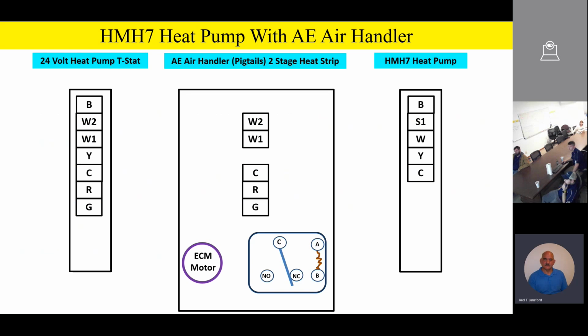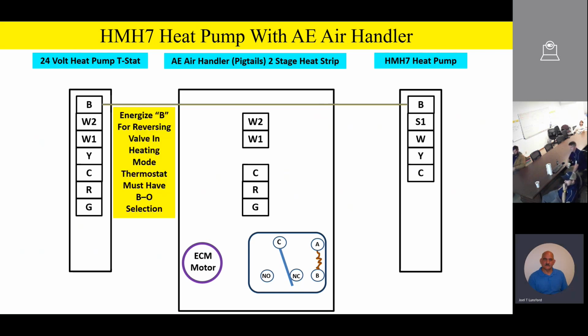Okay, so at this time, team, we're going to go ahead and just walk through wire for wire, hooking up the HMH7 with an AE air handler. And again, please remember the AE air handler is equipped with pigtail connections. In our example, we're also going to be featuring a two-stage heat strip, so there will be a W1 and a W2 for auxiliary heat. So from our thermostat, we're going to go from B to B outside, and that's going to be for reversing valve operation in the heating mode of operation. So be sure and set that thermostat up for B for heating.